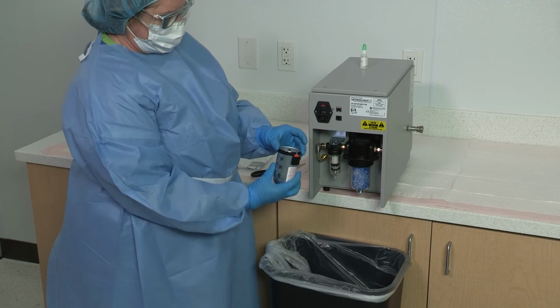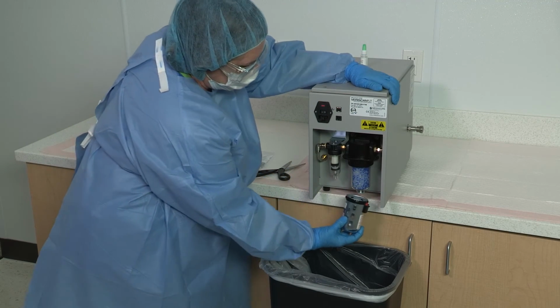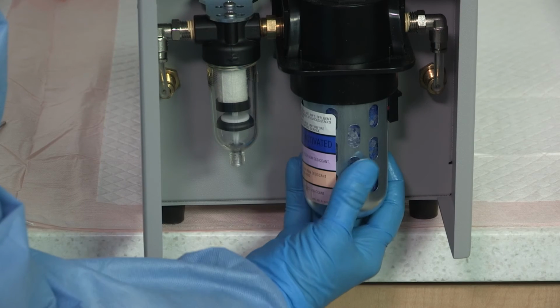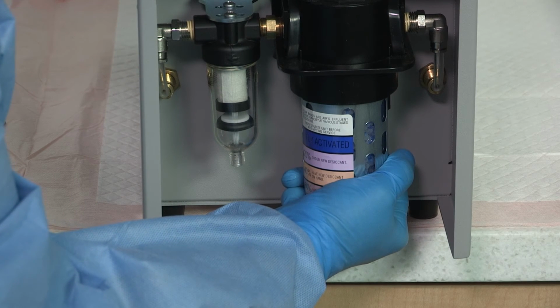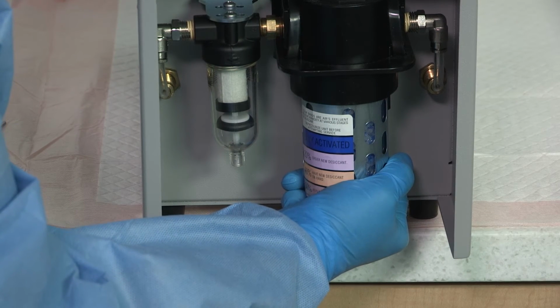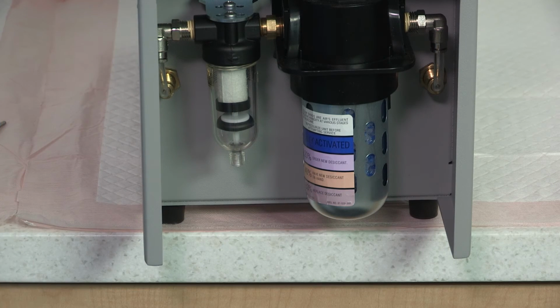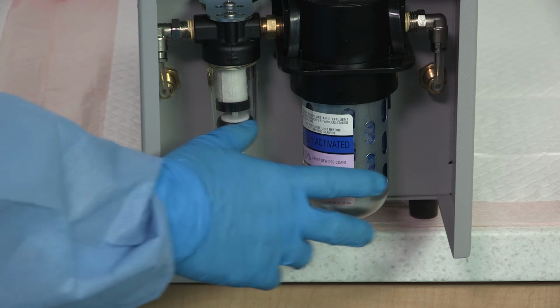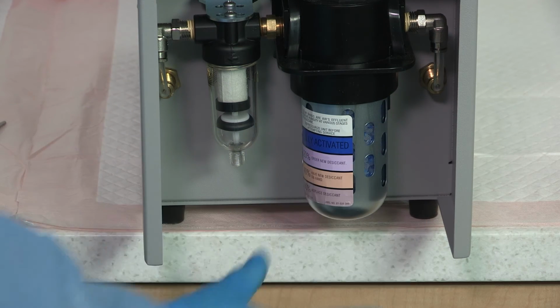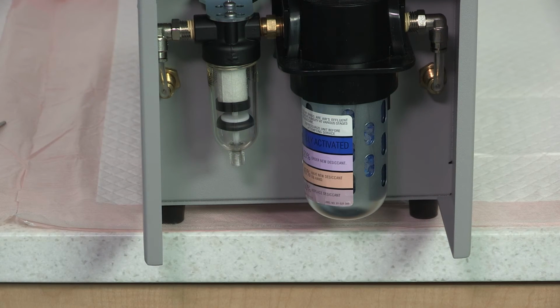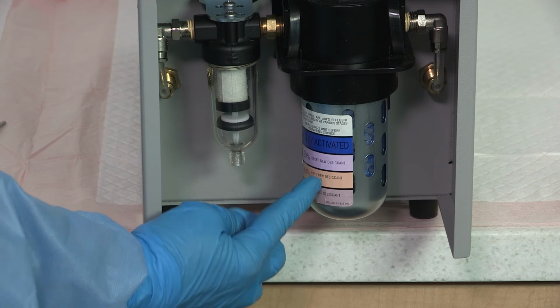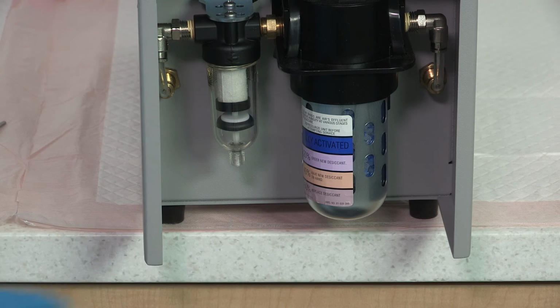Reattach the metal bulb housing by lifting it up and over the glass bulb. Pushing upward, turn the metal housing until it reaches a slot and the receptacle button clicks into place. Ensure the metal bulb housing is securely in place by pulling down on it. The glass drying crystal bulb can become dislodged during a leak test if the metal bulb housing is not properly in place. The color comparison chart identifying the drying crystal's color change stages should be facing outward.